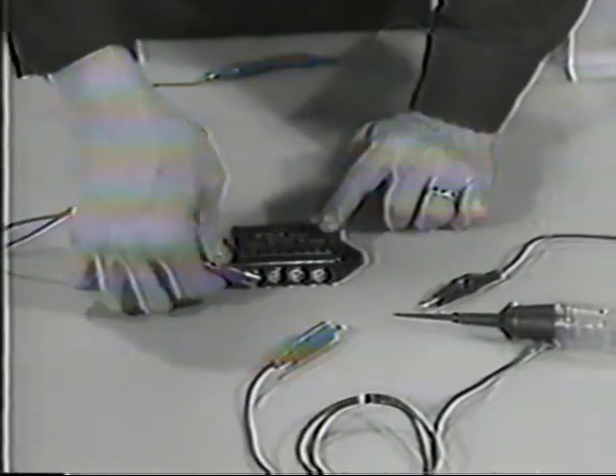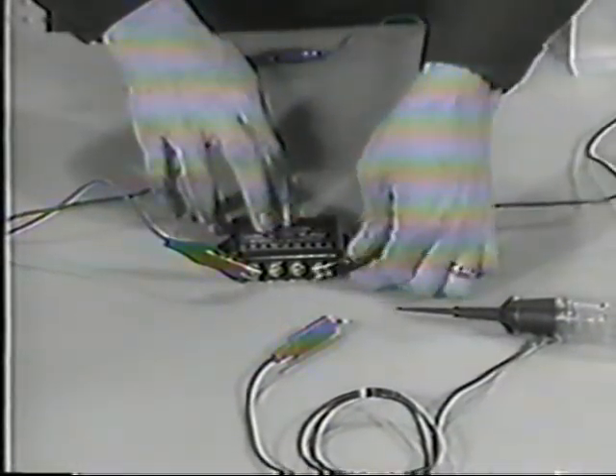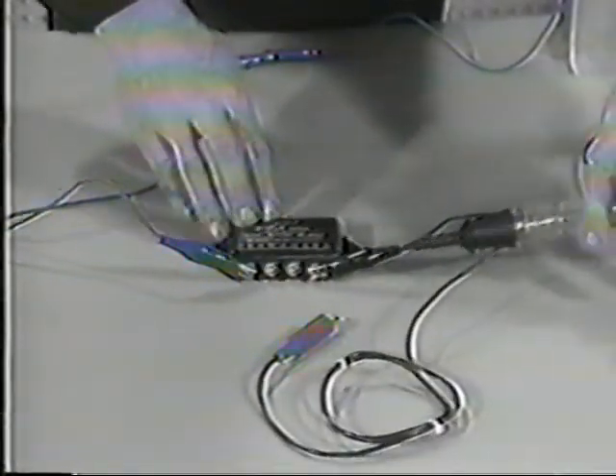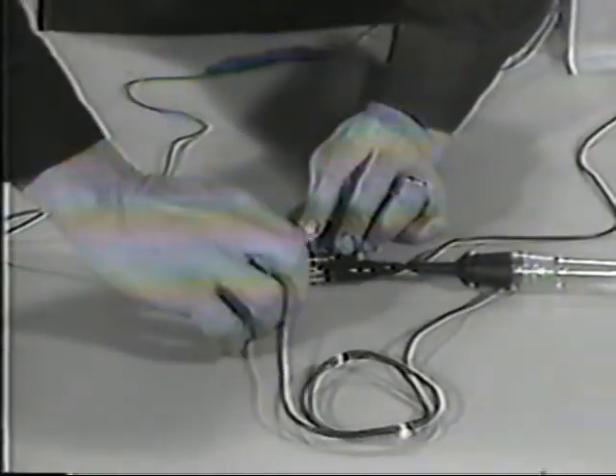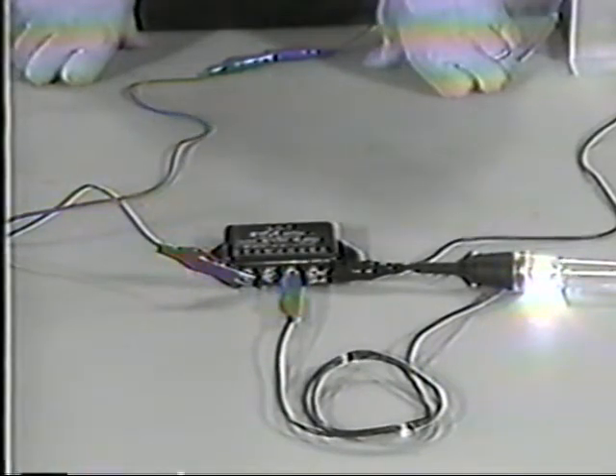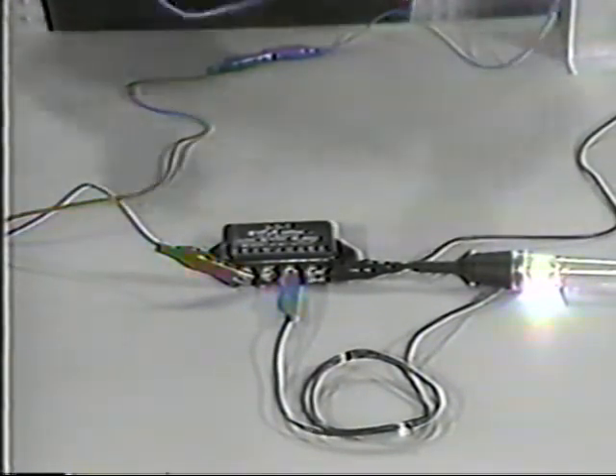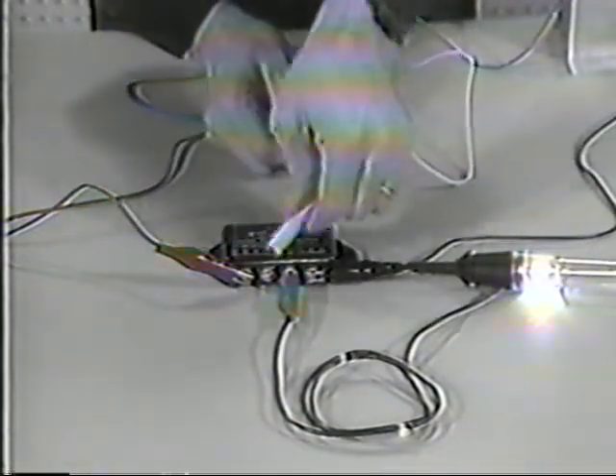Next, let's test the module used on the 90-30 alarm-only system. Begin by connecting positive battery voltage to post number 1, negative battery voltage to post number 4, the warning light or test light between post number 4 and module post number 3. The test light should be on at this time. At this point, connect terminal number 2 in the front to terminal number 4, which is ground, and the light should go out. In the rear of the module, connect terminal number 5 to terminal number 4, which is ground, and the light should come back on. Any module that does not act this way is defective.